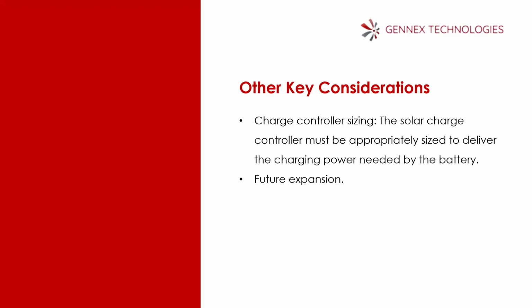If you have a battery whose minimum charging current, for example one that can charge in 10 hours, is 20 amps, you don't go ahead and get a charger whose maximum charging current is just 10 amps. That means it's going to take more than 20 hours before it's full, which is a waste of time. With lithium ion, you can even charge the battery within 3 hours if you have a charge controller with the capacity to pump that energy into it.